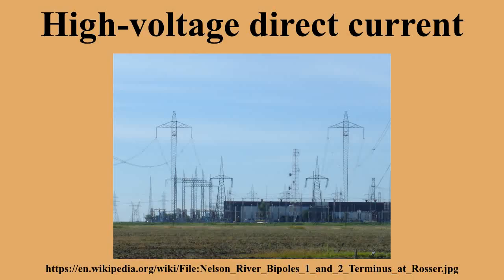Initially, all switches are closed, because the high-voltage semiconductor switch has much greater resistance than the mechanical switch plus the low-voltage semiconductor switch. Current flow through it is low. To disconnect, first the low-voltage semiconductor switch opens. This diverts the current through the high-voltage semiconductor switch. Because of its relatively high resistance, it begins heating very rapidly. Then the high-speed mechanical switch is opened. Unlike the low-voltage semiconductor switch, which is capable of standing off only the voltage drop of the closed high-voltage semiconductor switch, this one is capable of standing off the full voltage. Because no current is flowing through this switch when it opens, it is not damaged by arcing. Then, the high-voltage semiconductor switch is opened. This actually cuts the power. However, it is not quite 100% off. A final low-speed mechanical switch disconnects the residual current.